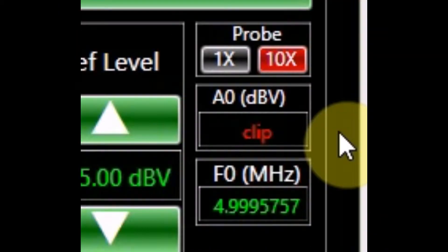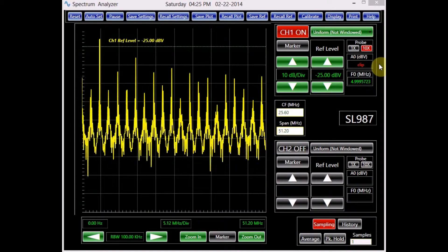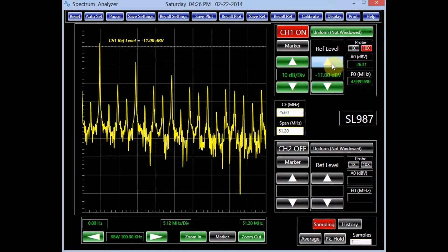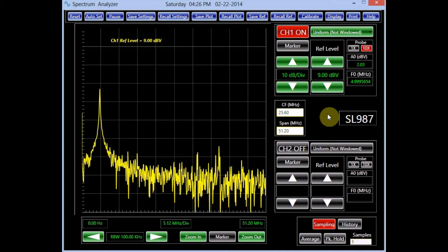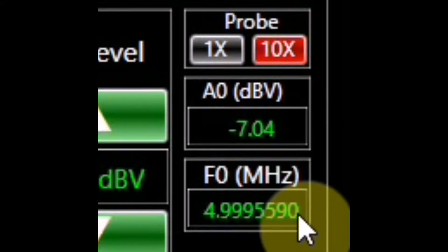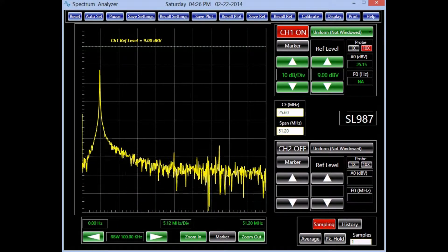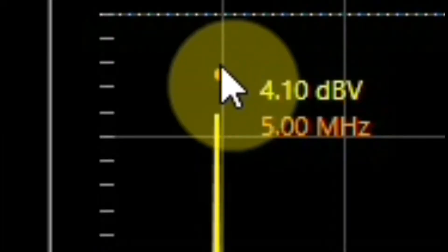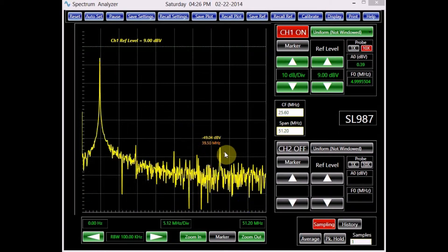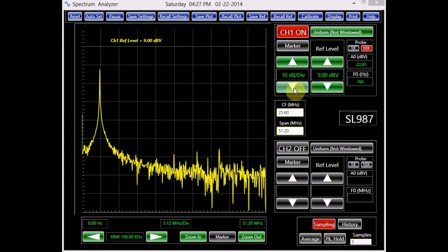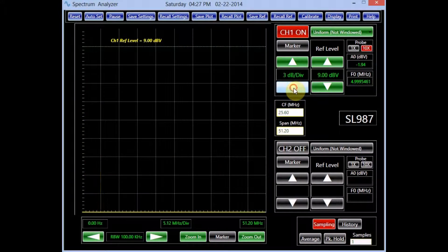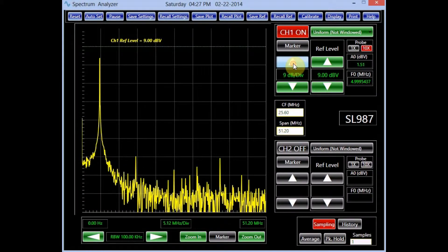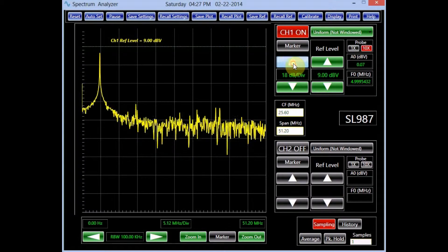The data information panel highlights this condition in red. Once the voltage setting is adjusted for channel 1 such that clipping does not occur, the peak amplitude of the signal and its frequency are displayed in their corresponding panels. The data corresponding to the position of the mouse is also displayed near its position in each channel's corresponding color. Channel 1 vertical resolution can also be adjusted from 1 to 20 dB per division.